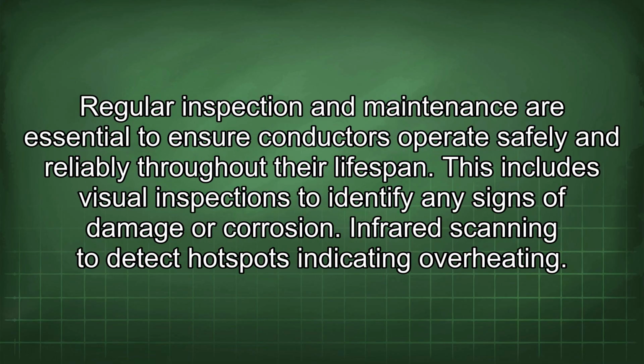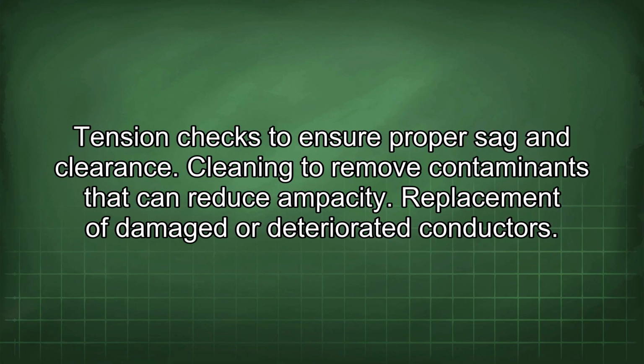Regular inspection and maintenance are essential to ensure conductors operate safely and reliably throughout their lifespan. This includes visual inspections to identify any signs of damage or corrosion, infrared scanning to detect hotspots indicating overheating, tension checks to ensure proper sag and clearance, cleaning to remove contaminants that can reduce ampacity, replacement of damaged or deteriorated conductors.